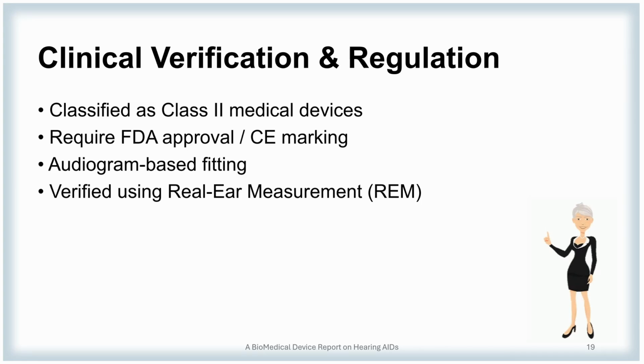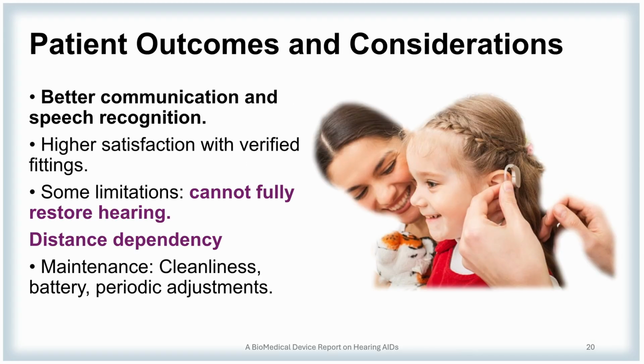So hearing aids are class 2 medical devices. They essentially require regulatory approval, audiogram-based fitting, and clinical verification using REM, real ear measurement. This distinguishes them clearly from consumer audio products. A properly fitted hearing aid leads to improved speech recognition, better communication, and higher user satisfaction. However, they do not restore natural hearing. Performance decreases with distance, background noise, and improper maintenance. This highlights the importance of realistic expectations.